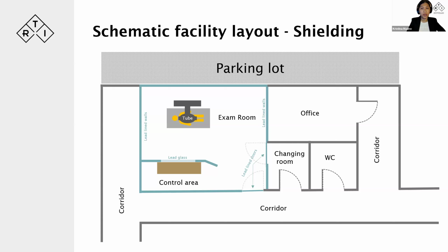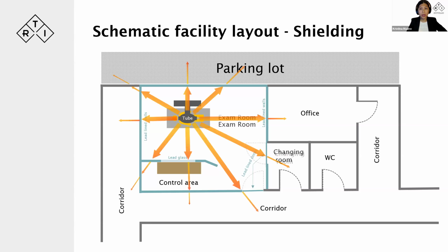The calculations are based on the equivalent lead thickness standard of lead glass. Usually during the shielding calculation, there's already a safe margin, making sure that the stray radiation does not penetrate through the shielding.